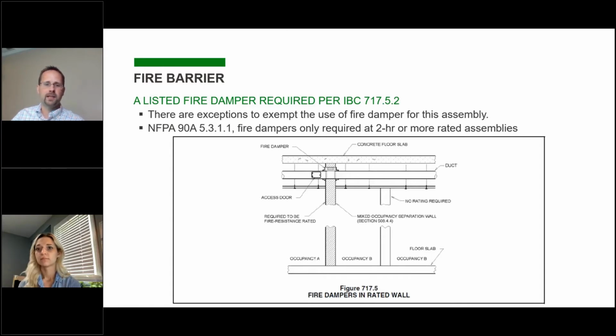One helpful piece of information is that in the 2018 IMC code commentary, they address this issue, and they state that if a duct goes through a 1 hour fire barrier and then has a flex that's just between that ductwork and the diffuser, that's no more dangerous and presents no more risk to occupants than if you had a grill that ended right at the wall with no flex. So based on that commentary, they lean towards the stance that a short piece of flex duct in the system does not invalidate this exception.